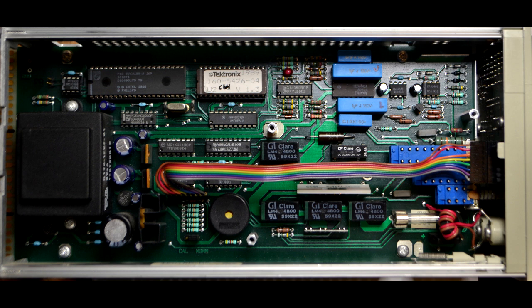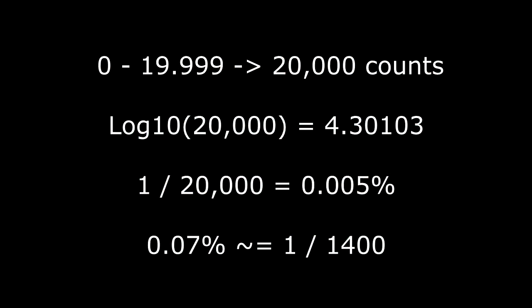This self-calibration method means that unless you have the correct sources, including an expensive Fluke meter calibrator, you cannot recalibrate a DM504A. I've read out the firmware EEPROM and the calibration constant EEPROM and given some thought to decompiling the code and deciphering which EEPROM values correspond to which ranges. But fortunately, except for the problems noted later, DM504As rarely go out of calibration.